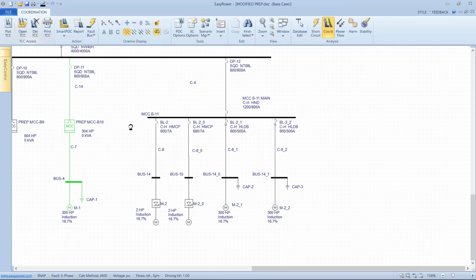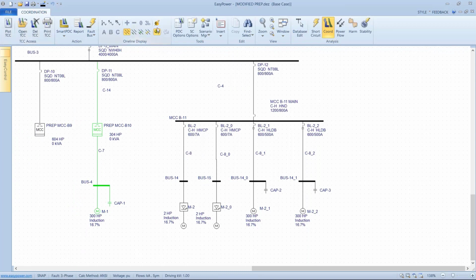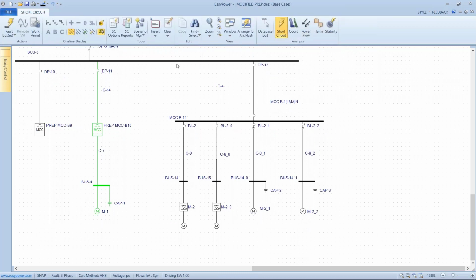Before I get too carried away, I do want to make another point. I emphasized the impact of the equipment duty, and here, if we look at this, if I take all the buses that are set up as motor control centers, looking at the current and fault them in short circuit, you can see that we have the ability to calculate equipment duty from that particular device, from that particular display.